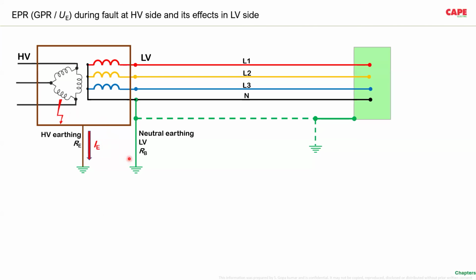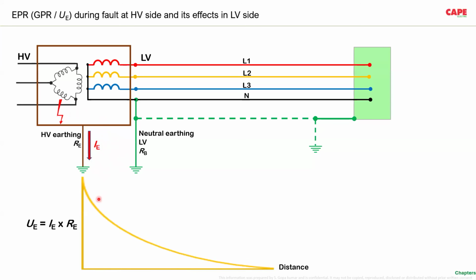The fault current IE is going to the earth electrode. There is a voltage gradient. Gradient in the sense that the potential of RE, where I'm moving the cursor, the potential of that particular point goes to a very high level, which is equal to IE into RE. UE is the GPR or EPR, earth potential rise, which is equal to the multiplication of IE, the earth fault current, or the current which is flowing to the earth electrode.